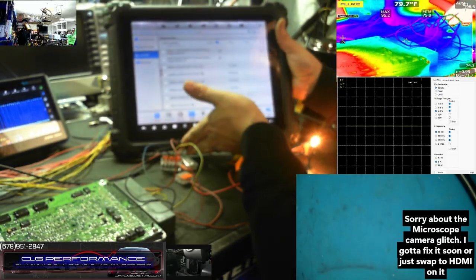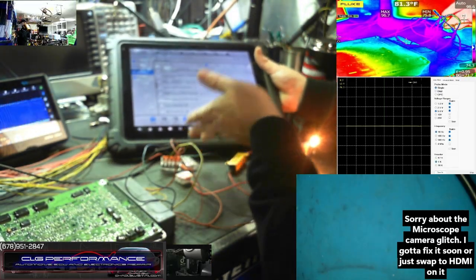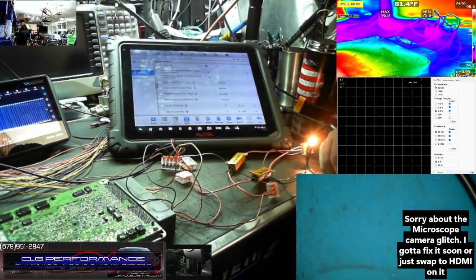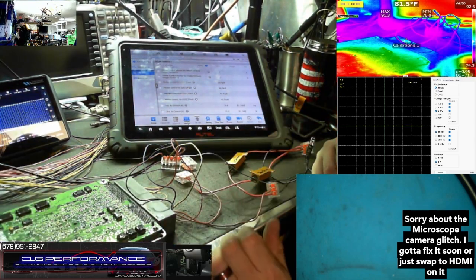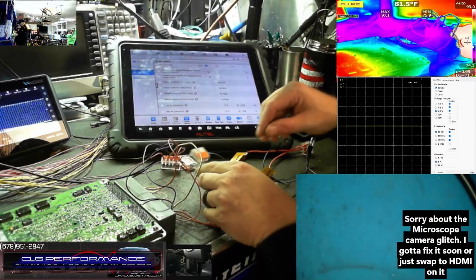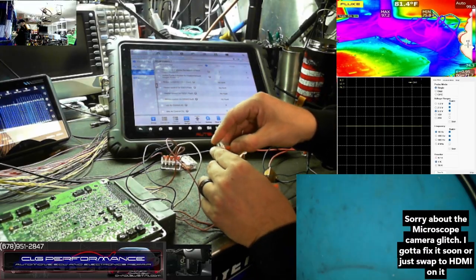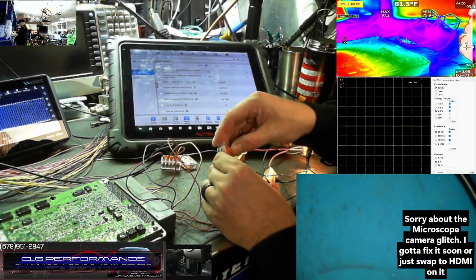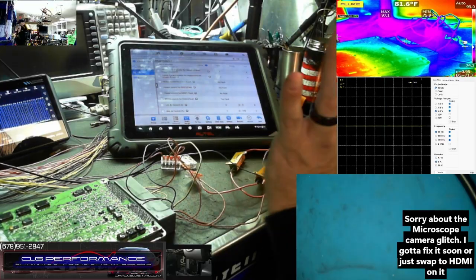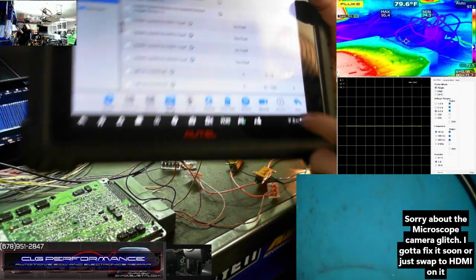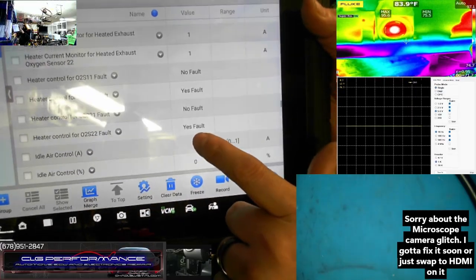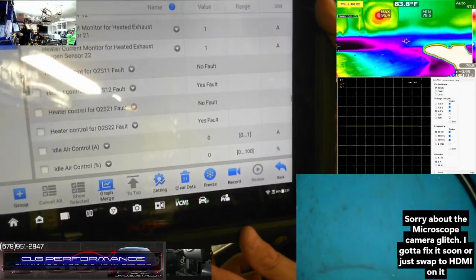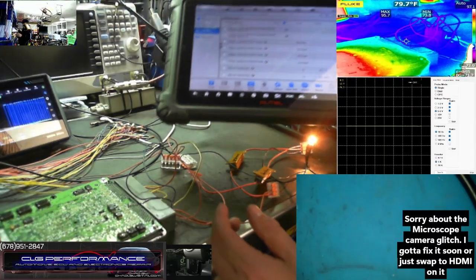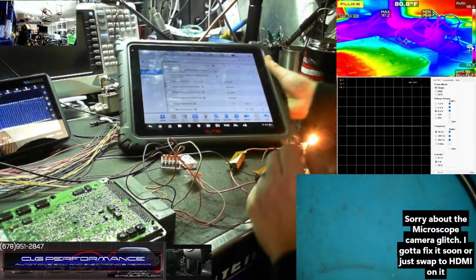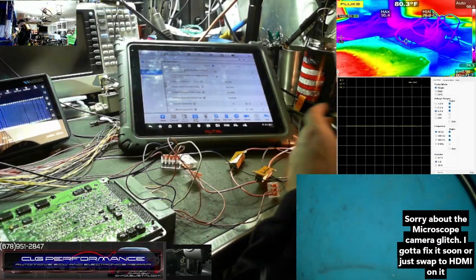Now let me go over here and I'll just do the downstream ones by itself. Let's reset this again. And let's just do the downstream intermittent. That's all I had to do, barely get a disconnect on it, and now it's saying fault on both downstream sensors because they're paired grounds on the wire diagram.